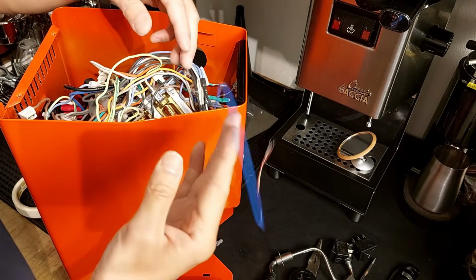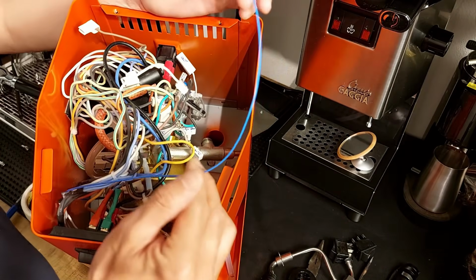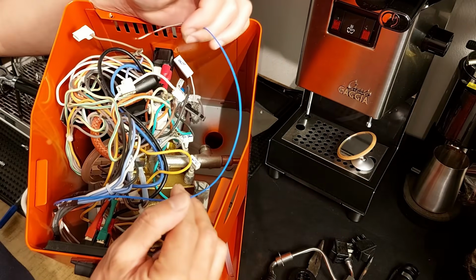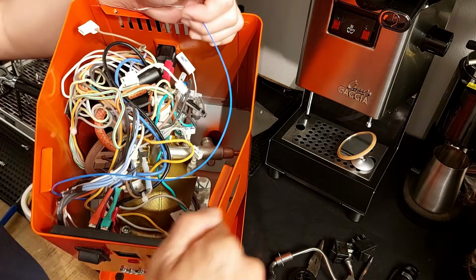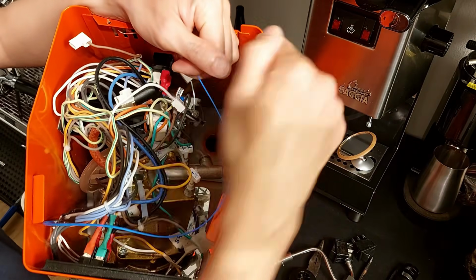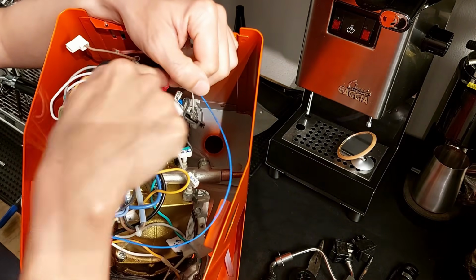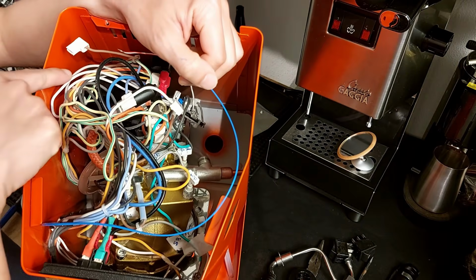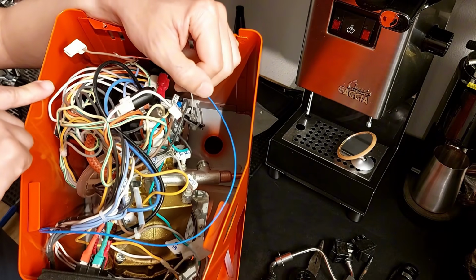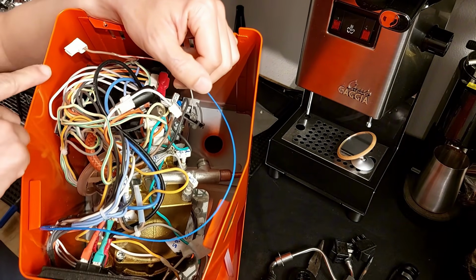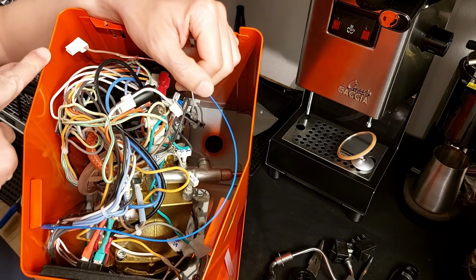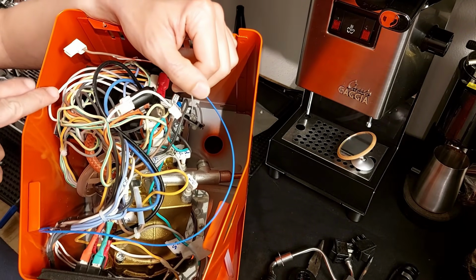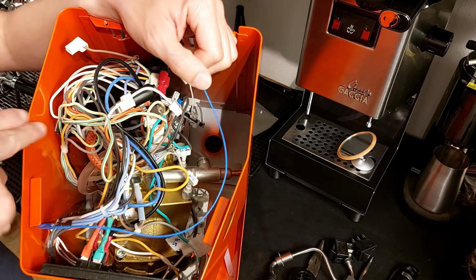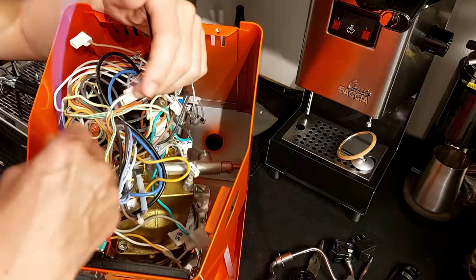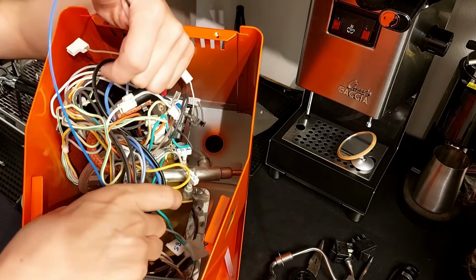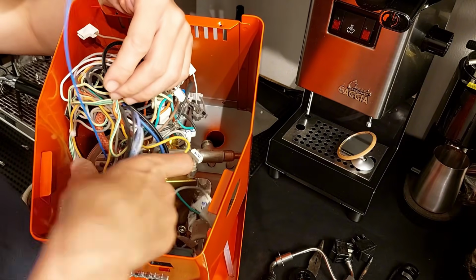Now we need to route this cable for the thermocouple around the front of the machine and not on the back, which would be close to the pump area and subject to interference from the high voltage wires and electromagnetic interference from the pump and solenoid valve. So let me route this cable now since it's easier at this stage.